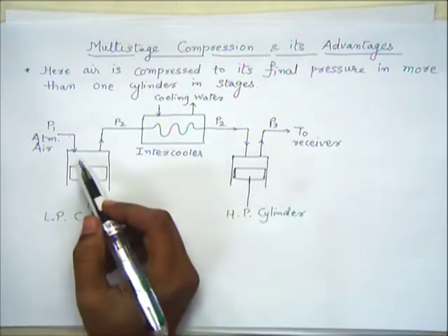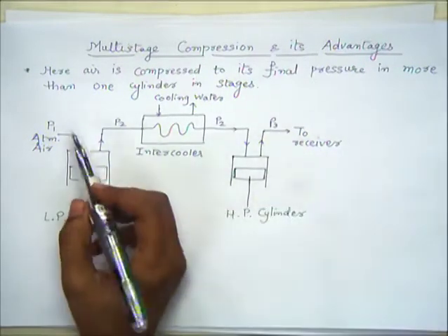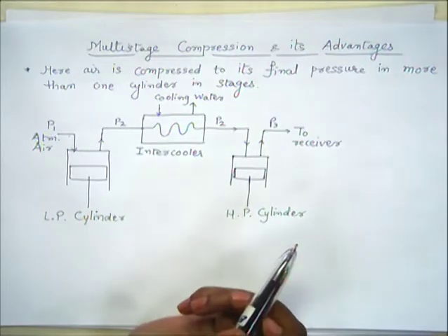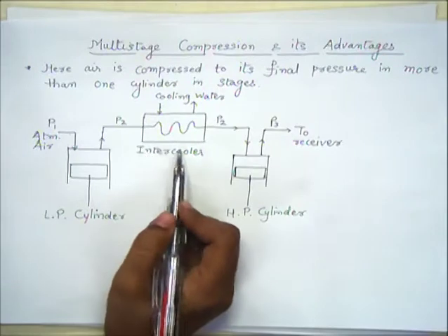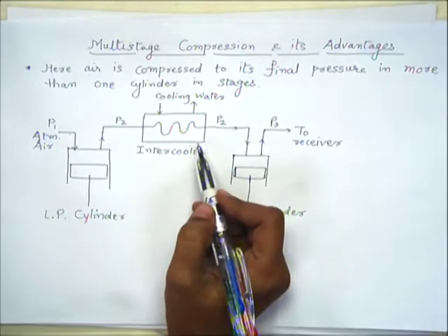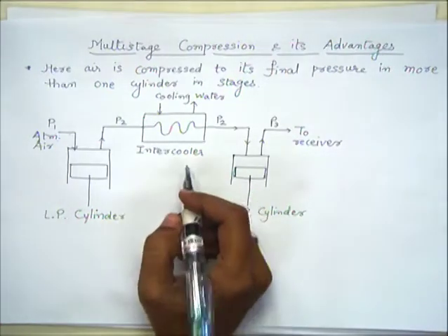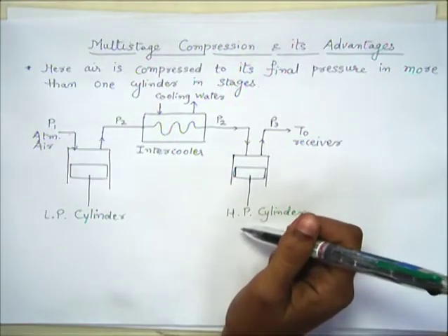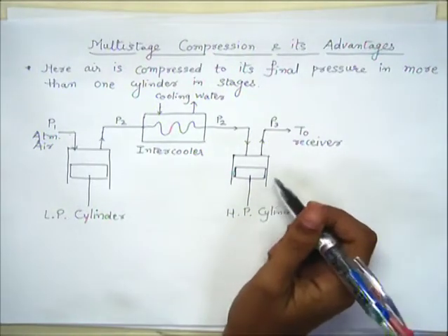For example, if the final required pressure is 5 bar, we compress from 1 bar to 2 bar in the low pressure cylinder. P2 is 2 bar; the air then passes through the intercooler where we approach isothermal compression by reducing the temperature. Then in the high pressure cylinder, pressure is increased from 2 bar to 5 bar.